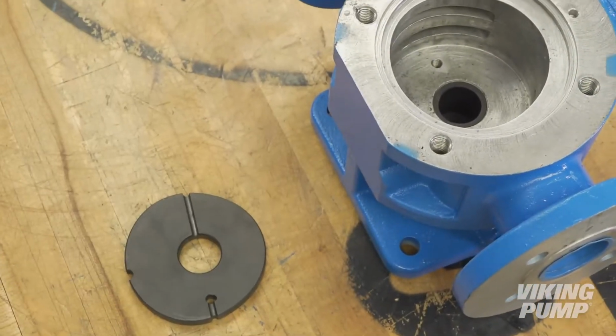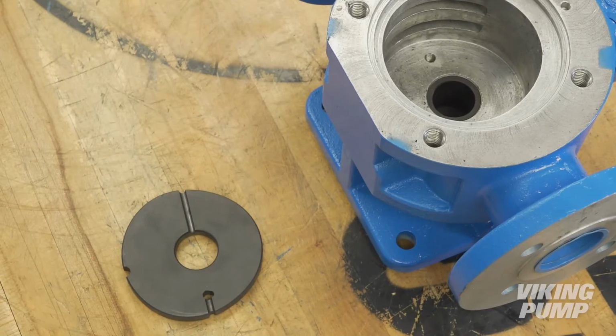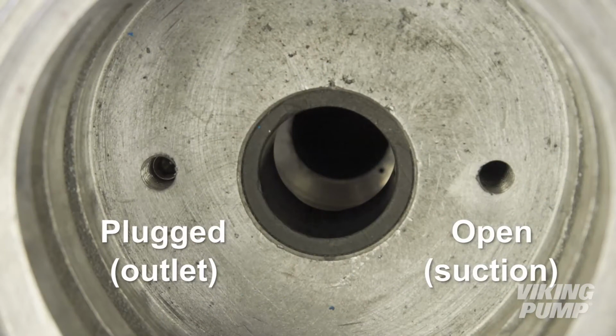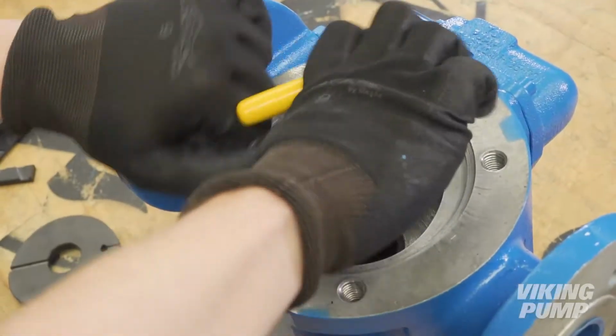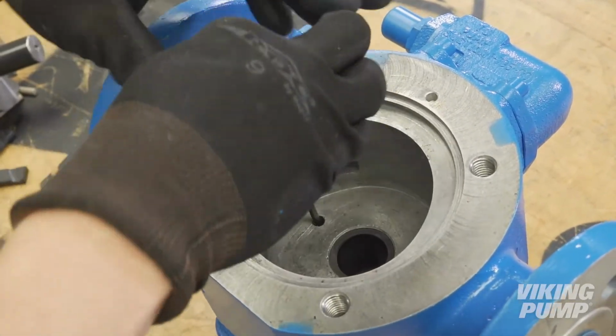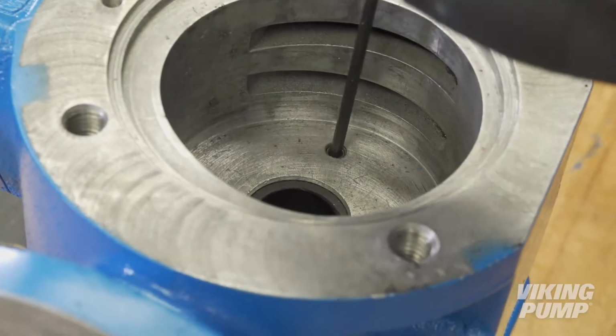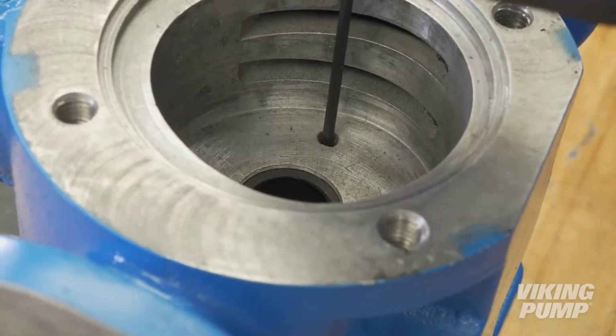Each carbon disc will need to be flipped so that the holes line up with the open holes on the suction side of the pump. At the back of the casing, you will find another set of internal flow path holes, with one of them being plugged. Remove the plug with an Allen wrench and reinstall in the other hole. You can now reassemble the pump.